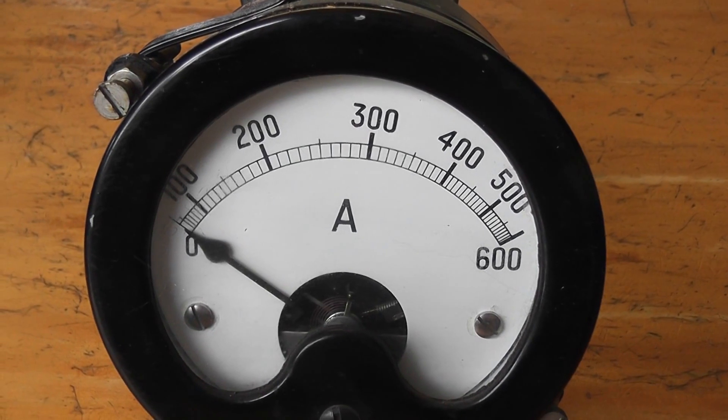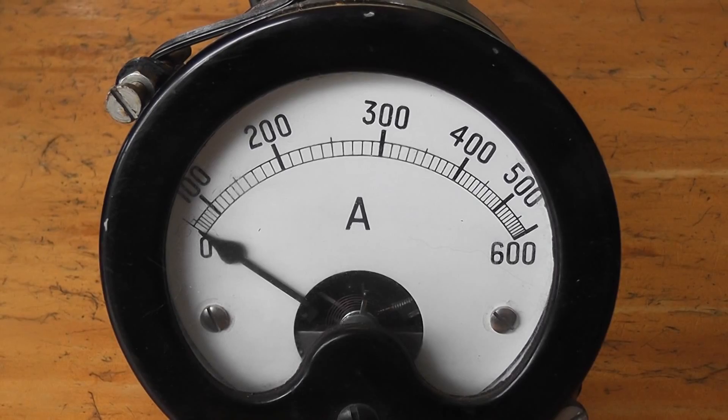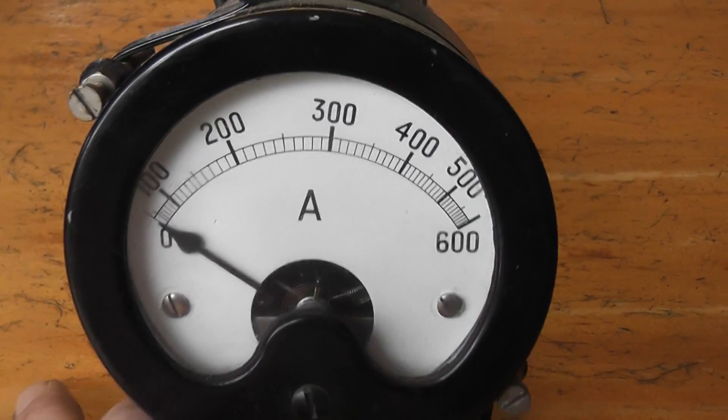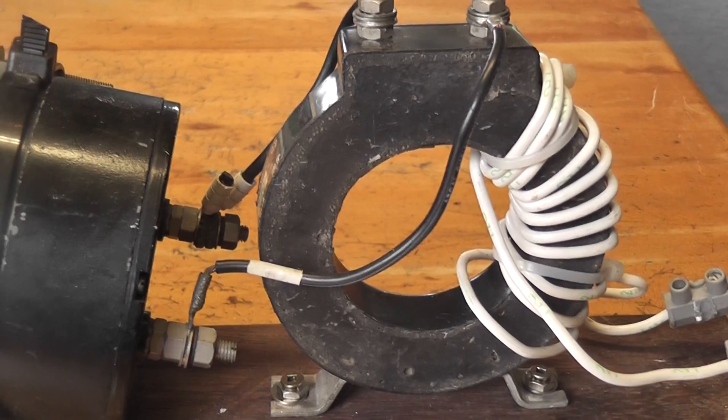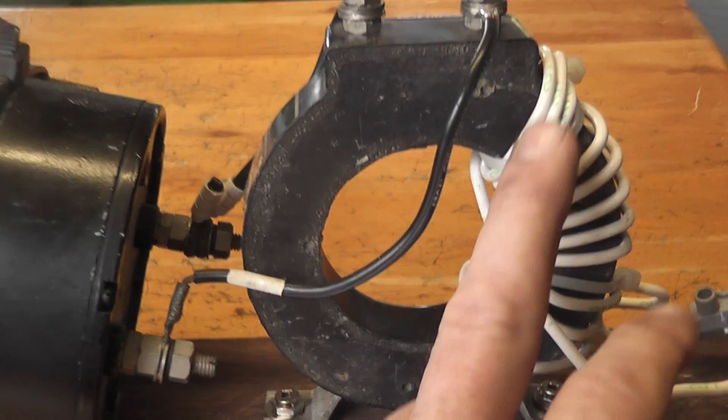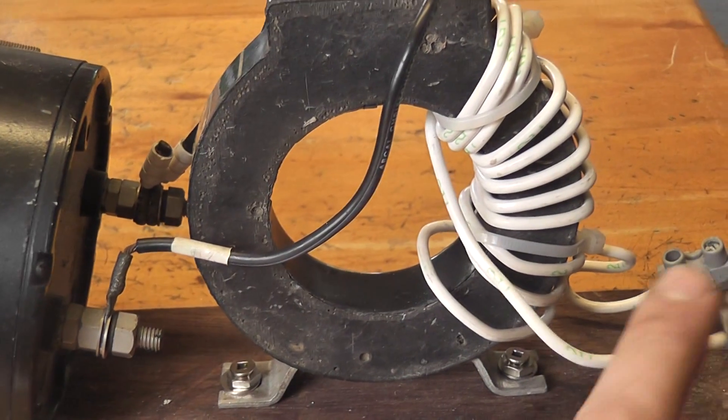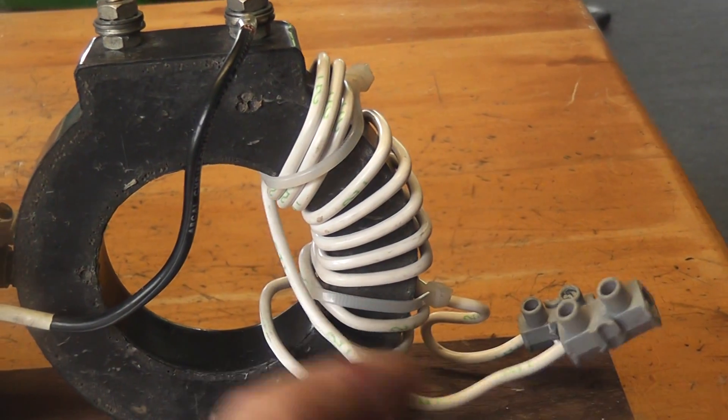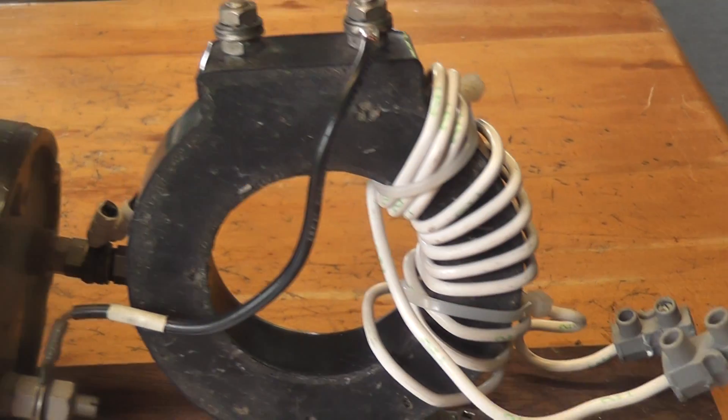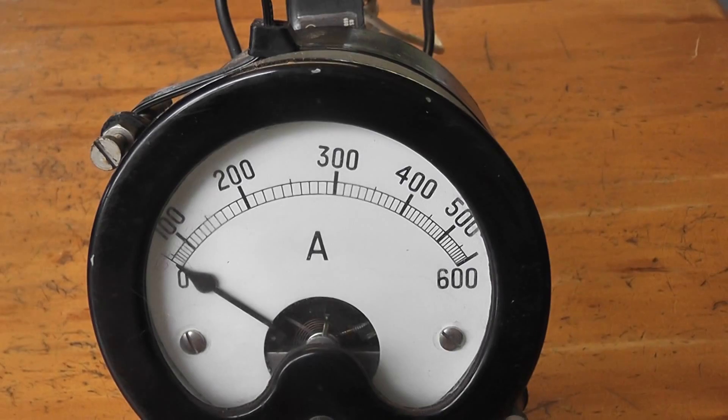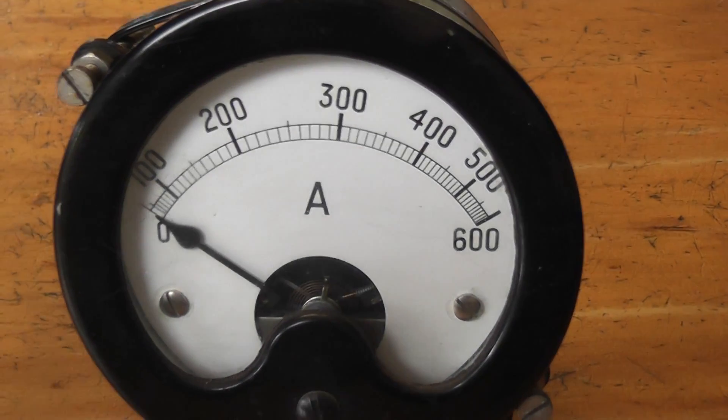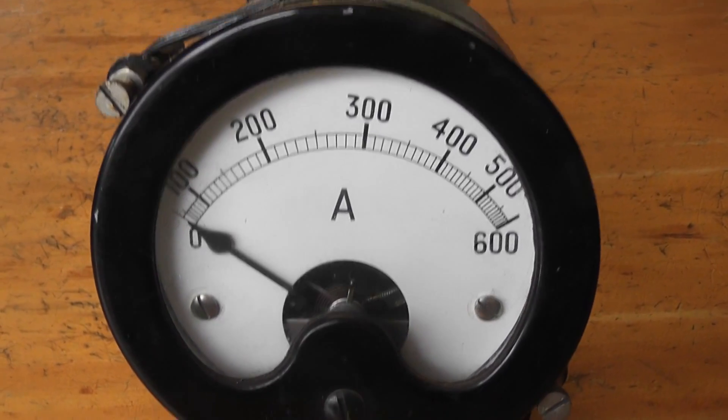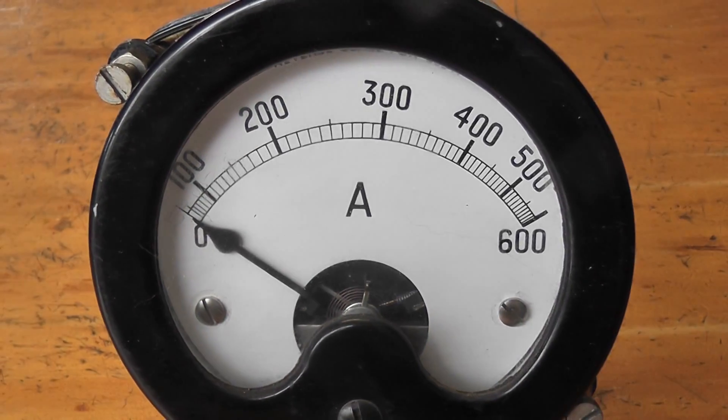So in this particular case I want to measure 20 or 30 ampere with a 5 ampere meter. What I have done on this setup is I've used a 400 to 5 ampere CT and I put 10 turns. This is going to be my primary coil. So if I put up to 40 ampere through this bar, 40 ampere gets 5 amp to the meter. That means the meter will read 400 in this particular case when 40 ampere goes through that coil wound. But then the reading is scaled by a factor of 0.1 which equals 40 ampere.